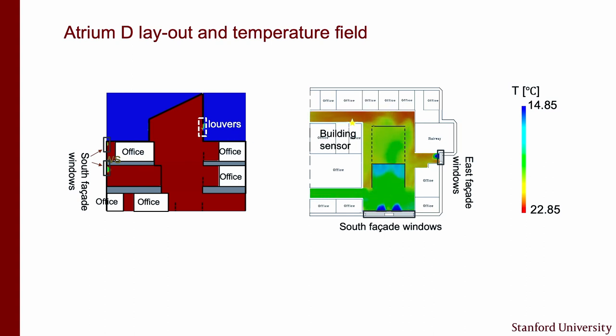We had been doing about half a year of simulations and validation work, wondering why we kept seeing faster temperature decreases than our measurements reported. It turns out it's related to where the building sensors are. This matters not only for validation of our models but also for control, because where you put your sensors determines your control.